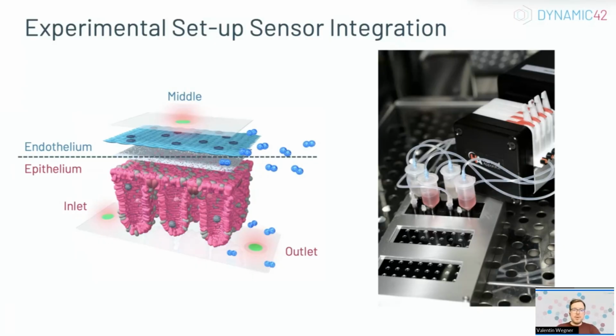As I showed you before with our chips with the sensor spots, we have one in the top channel, two in the bottom channel, one on the inlet where fresh media enters the chip, and one on the outlet where you can measure how much oxygen was consumed within our chip. And how to set it up in the incubator is basically quite easy. You have your chip connected to your pump, and you simply place it on the mounting frame. There are only three positions you can choose from, but there's no moving at all.